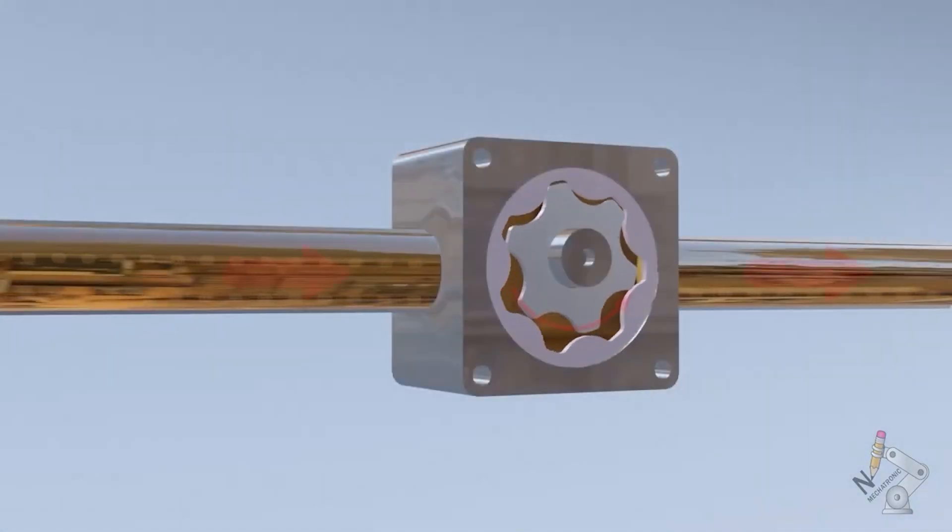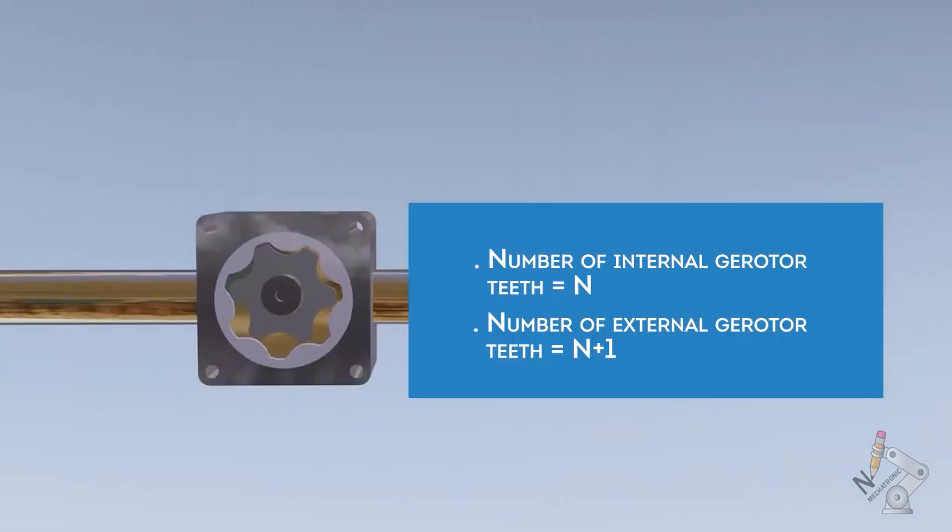The operation is very similar to the internal gear pump, with the difference that there is no crescent separating the gear teeth. The number of teeth on the outer rotor always exceeds the number of teeth on the inner rotor by one.